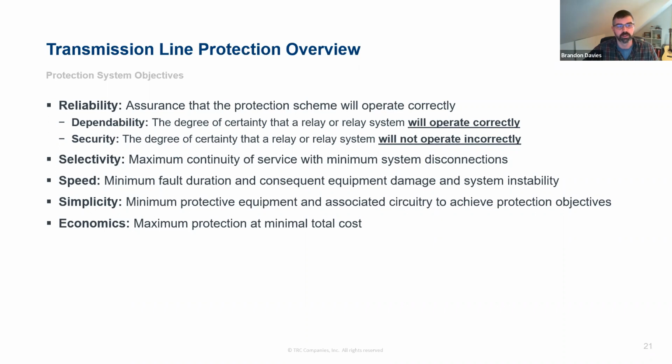If you put the two systems in two different buildings, you could drive a truck through the panel lineup of one, and the other one would still operate with no interruption of service. That's the rigor that they put into the redundancy requirements at the bulk power system. But that's not required everywhere. It's really just for those really critical facilities.